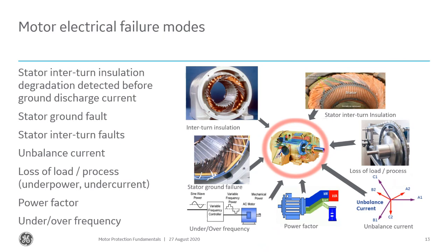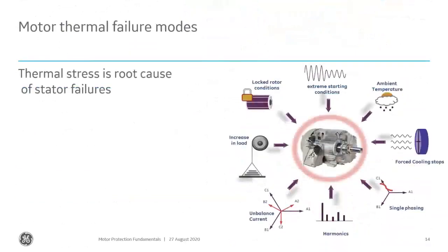If whatever the mechanical element is that you're driving, whether it's a fan or a pump, loses whatever it is that it's providing that drive to, then you may want to trip off your motor and examine your process.